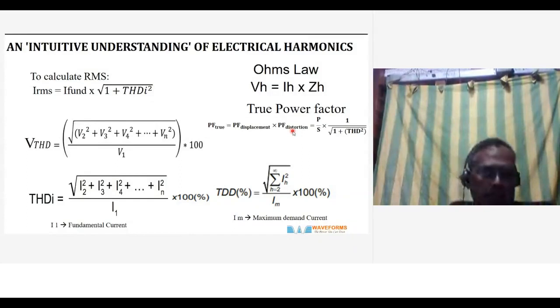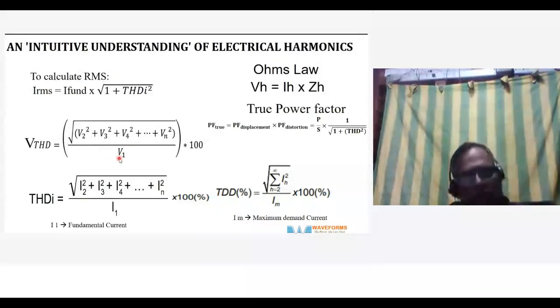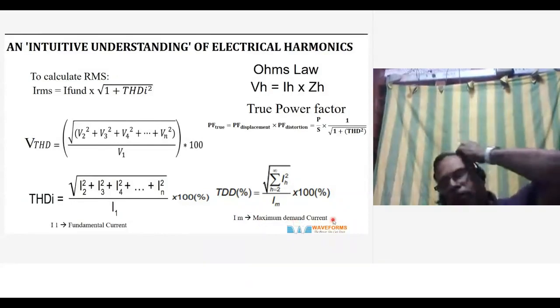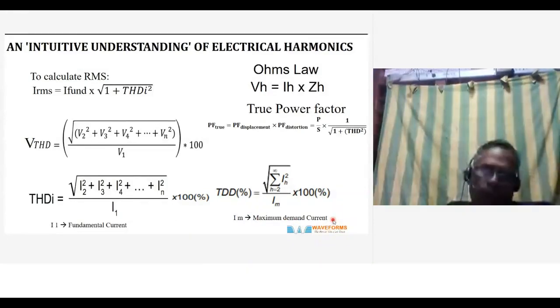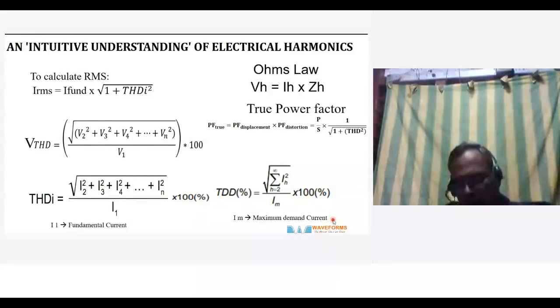So the voltage THD and THDI are calculated this way. From the second harmonic to the nth harmonic, you add the squares, take the square root of that, and divide by the fundamental voltage. Similarly, the calculation is done in the same way for the current for calculating THDI. So this is the THDI, and then you have total demand distortion. So the harmonic current is divided by the average demand. The maximum demand current, say the average of 12 months, is taken, and then they average it out, and this is called total demand distortion. So there is a difference between THDI and TDD. I'll come to that a little later.